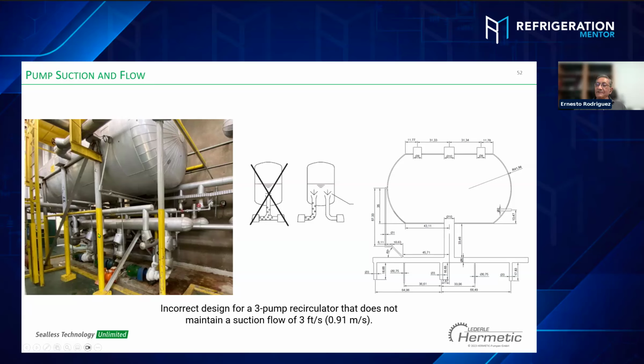Now we have 3 pumps running, and those pumps fight with each other. This is the reason they are replacing a pump right now, because when this pump is running, it can create turbulence and make this pump fail, or when this pump is running, it keeps those top pumps empty with not enough fluid. That is a big mistake. If somebody is going to work with pumps in CO2 or ammonia and they have too many problems, check why. The same problem is at the different vessel right here. The pipe diameter is too small. They don't maintain the velocity of the suction of the pump, and the pumps are failing. I see this many times.